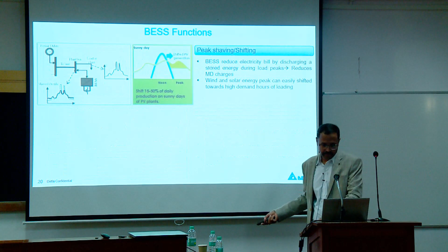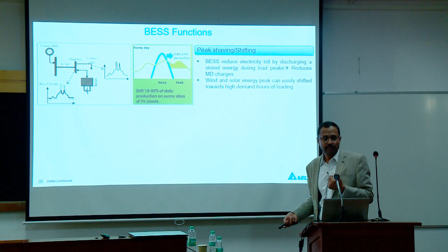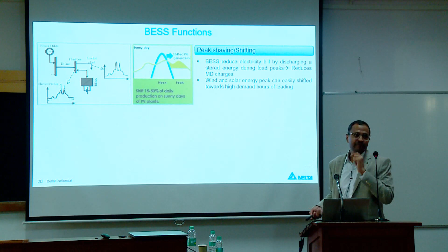Then comes peak shaving and shifting. Typically in industry, whenever you turn on furnaces for only 10 to 15 minutes during the peak of the day when other loads are also present, you start demanding peak power. Just because of this peak power you have to pay extra money, which we call MD, maximum demand. When you buy electricity from the board, if you draw any peak power for an average of 15 minutes, that is considered your maximum demand. Even if your connected load is 100 kVA and you draw 120 for just 15 minutes, you are charged for that 120 MD for the whole month. To avoid this, we normally do peak shaving.